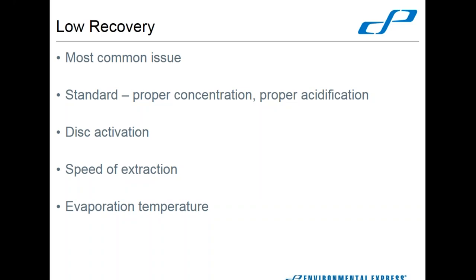Disc activation—we talked about that. That can be a little bit tricky in making that happen correctly. You do want to make sure you remove all your activating solvents off of there, but you have to replace it with water and keep that disc damp while you're removing the methanol. If part of it goes dry, that can adversely affect your recovery. Usually if you're just under 50 percent, somewhere in the mid to upper 40 percent recovery, that's often indicative of a poor disc activation. You can troubleshoot that easily by getting a sample of the pre-activated disc that we have, the UltraPrep line, and giving those a try.